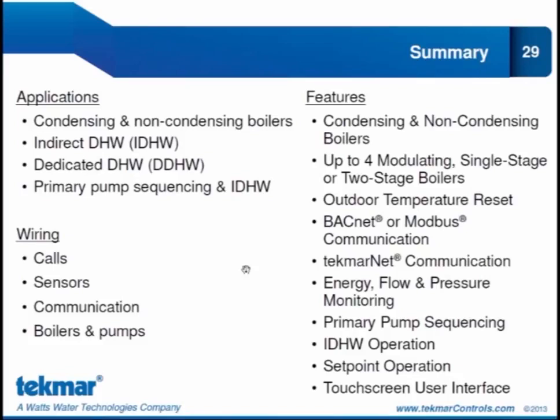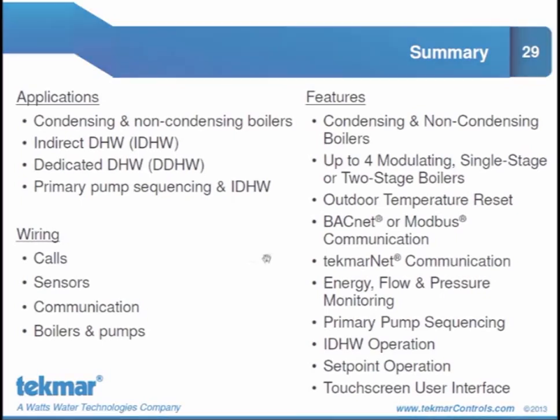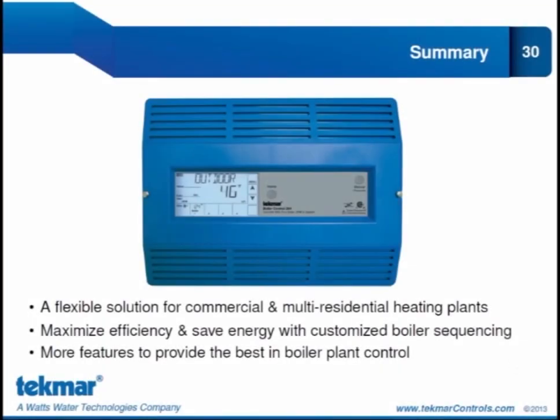And lastly, we looked at the wiring, how we wire calls to this control, how we wire the sensor input and communication, and how we wire the boilers and the pumps. In particular, we looked at how there are 4 boiler banks, and each boiler bank has 6 terminals so that we can wire up the type of boiler that we have.